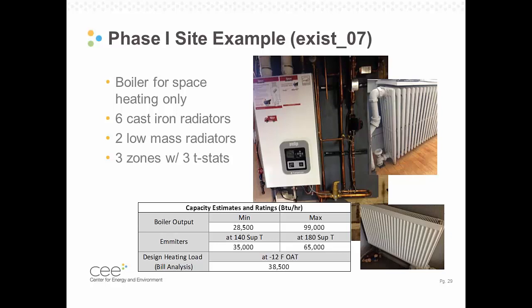We also did a detailed billing analysis at this house and found that the requirement of the house to keep the house warm at negative 12 degree outdoor air temperature was just shy of 40,000 BTU per hour. And so then we went through the house and did a pretty detailed characterization of the emitters, and you can see there the range of supplying 180 degrees temperature to all those emitters will give us about 65,000 BTU per hour. If we drop that temperature by 40 degrees, we cut that emitter capacity about in half, but we still give 35,000 BTU per hour, which is pretty close to that design condition for the home.